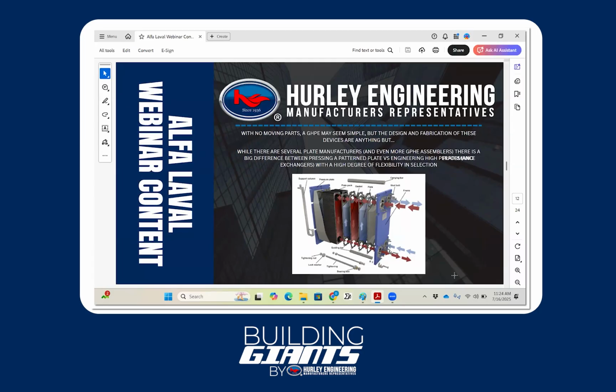Yeah, how they make up that plate and frame heat exchanger. You've got your end plates that hold the plate pack itself. Then you've got some type of expanding bar or rack hanging bar at the top, and bolts that you can tighten in order to meet the tolerance the factory wants to make sure that plate pack is closed correctly.